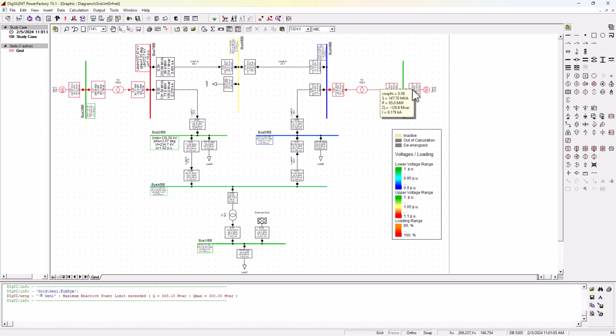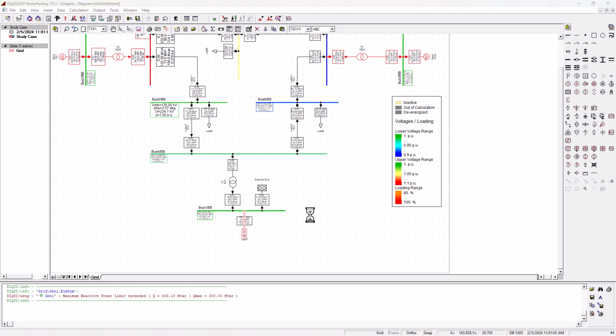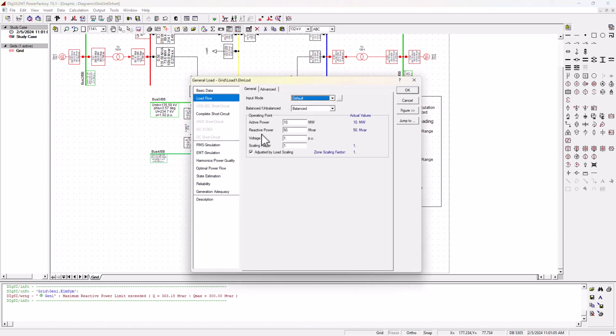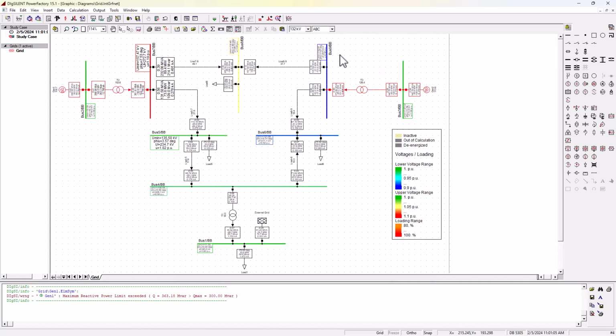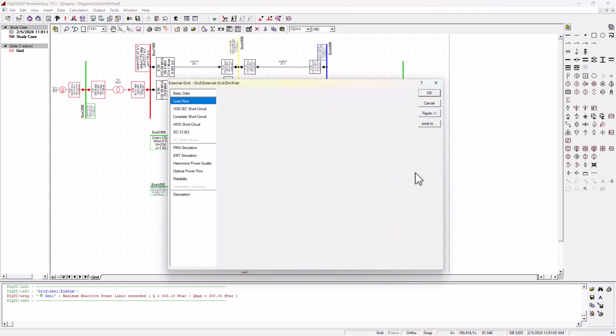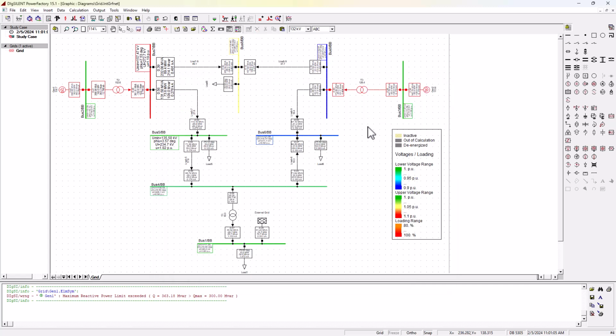This is what's causing this generator to absorb reactive power, to try to keep these dropping voltages to the limit of 1 per unit, which is set by the reference machine here as well, which tries to regulate the limits that are set by the generator itself and the reference machine that we've got here, the external grid. So that is the cause of this generator's negative reactive power.